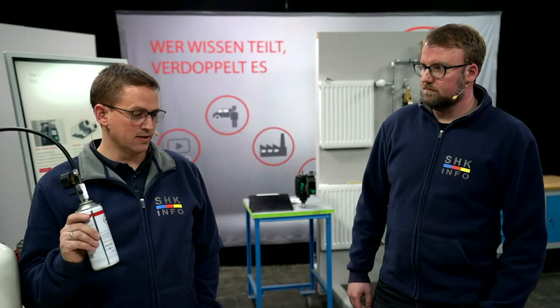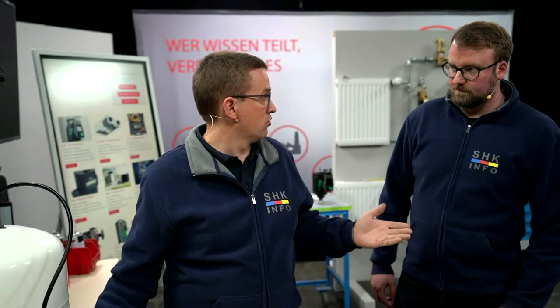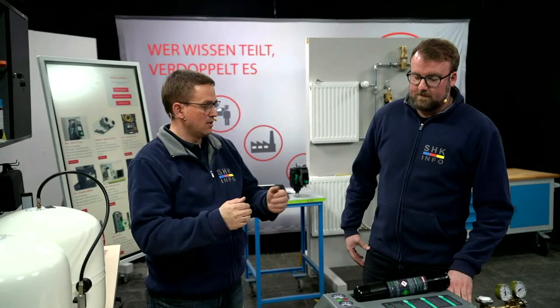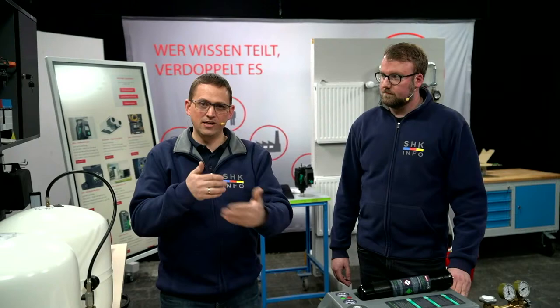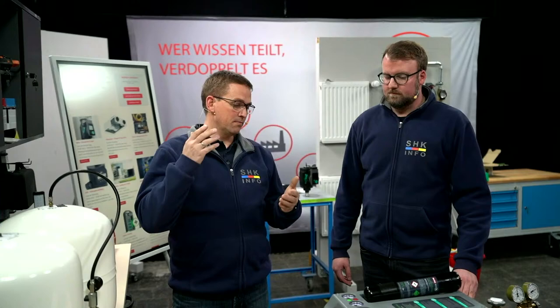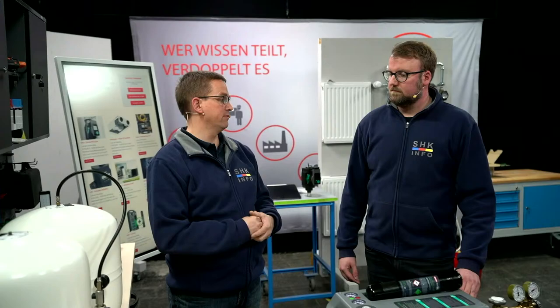Das ist auch noch ein wichtiger Punkt: Wir haben relativ viel Dosenmüll. Die Dosen sind Sondermüll. Diese Flaschen hingegen können einfach mit dem Schrott entsorgt werden. Von daher ist da natürlich ein großer Umweltaspekt dabei. Und wir haben viele Vorteile vom echten Stickstoff gegenüber dem Kältemittel. Der Stickstoff hat größere Moleküle – wenn ich mit Luft füllen würde, habe ich da auch einen Sauerstoffanteil, und der würde durch die Membrane diffundieren. Das ist der Druckverlust, den wir in den Gefäßen haben, wenn man mit normaler Druckluft arbeitet. Stickstoffmoleküle passen nicht so durch die Gummimembranen durch, deswegen ist die Druckhaltung besser. Viele Hersteller geben auch vor, dass die Gefäße mit Stickstoff befüllt werden sollen.